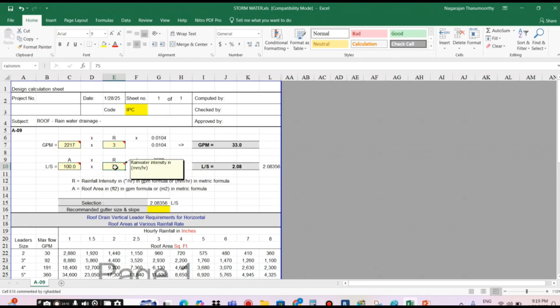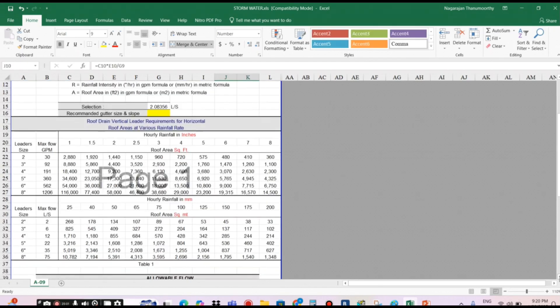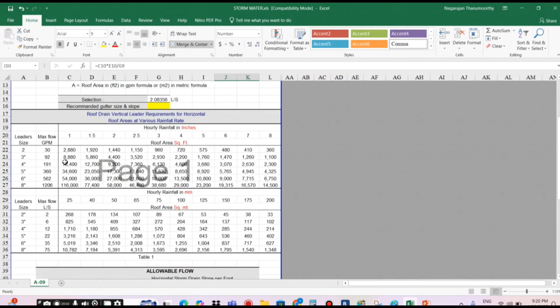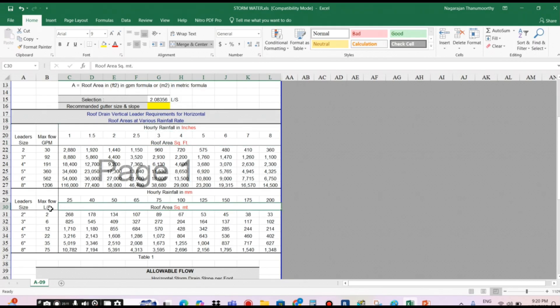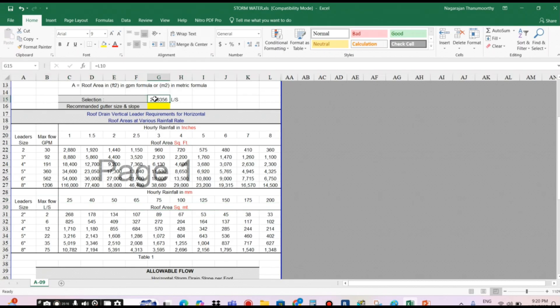Three inches equals 75 mm, so both answers are the same. Moving down, this section is for square feet and inches per hour. I entered the area in square meters and got the answer in liters per second — 2.08356 liters per second. In stormwater drainage, there are two pipe types: the leader pipe and the surface runoff pipe, also called the offset pipe.